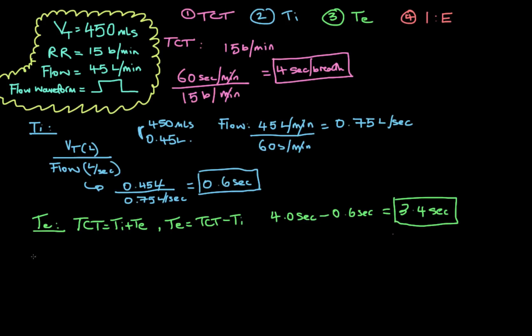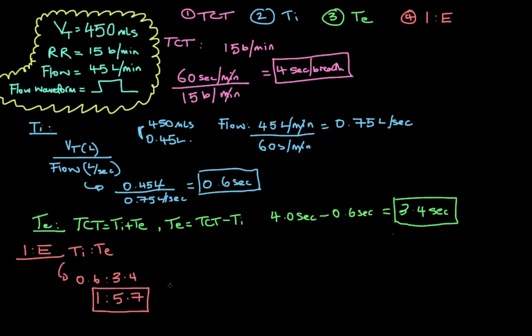Finally, let's calculate our IE ratio — simply a ratio of inspiratory time to expiratory time. We have 0.6 seconds of inspiratory time to 3.4 seconds of expiratory time. Using a calculator: for every 1 part of inspiration, we have 5.666, so approximately 5.7 parts of expiration. Our IE ratio is 1 to 5.7. I chose this example to show that the IE ratio isn't always a whole number like 1 to 5 or 1 to 4 — it can be 1 to 5.7, but the inspiration part is always 1.